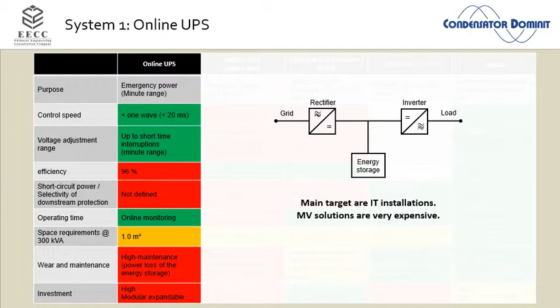They purchased a 5 megawatt UPS system for 5 million euro. And afterward they purchased filters for another €500,000, and another 500,000, and another 500,000. And finally they purchased filters for 5 million. End of story. Now the filters are not running anymore, and the UPS system is not running anymore. It's very difficult to run an industrial process behind a UPS. So okay, then we have other options.